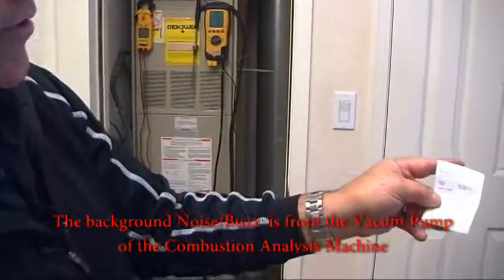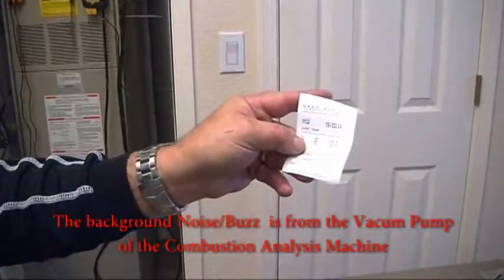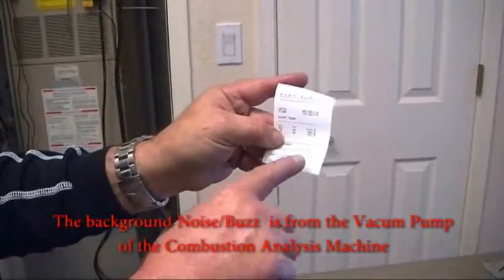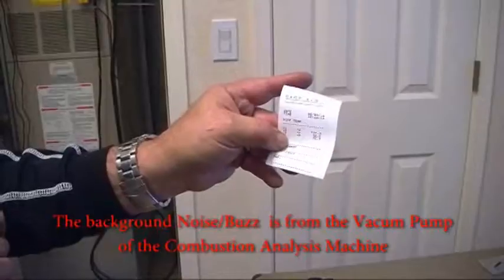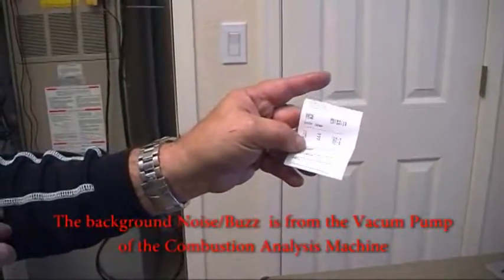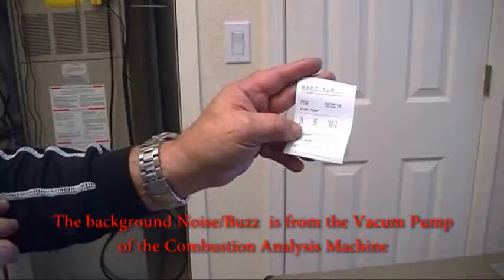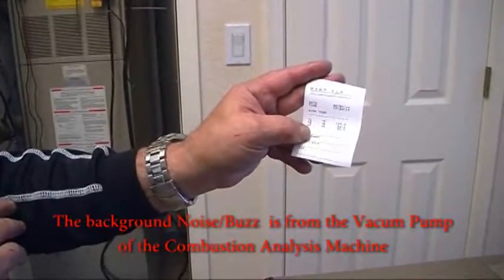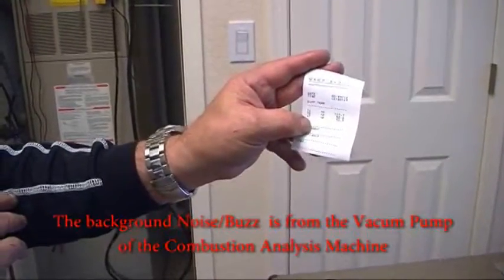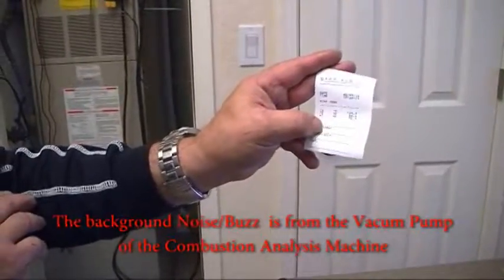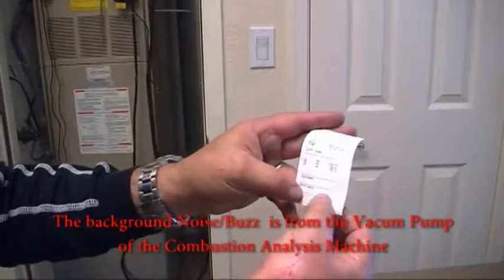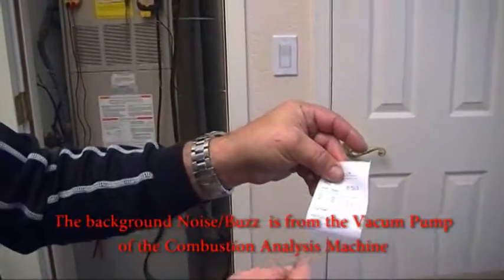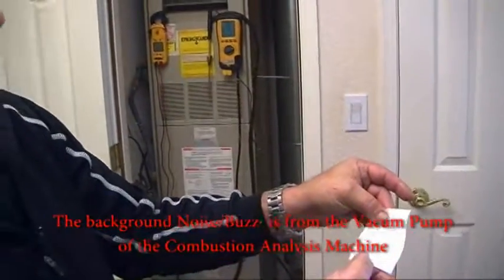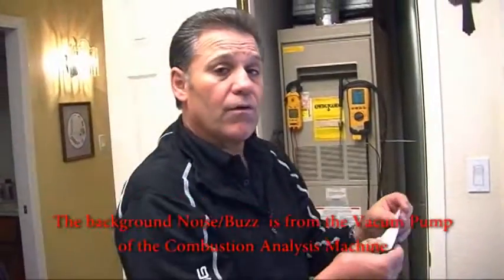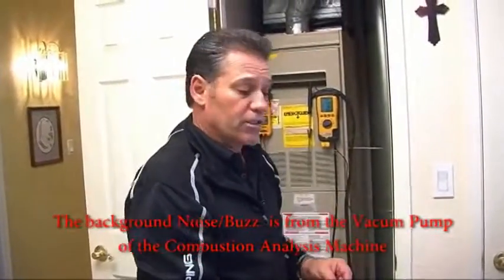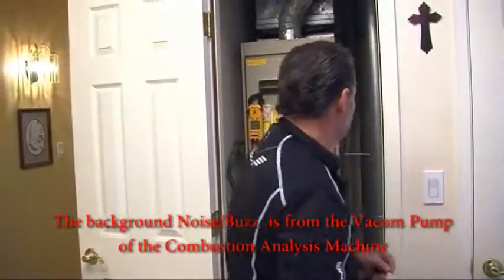It's February the 4th, 2016 at 12:08:14 p.m. Our delta T is 92.9. It's really right where we want it. Our supply air going out is 144.9 or 145 degrees, and our return is 52 degrees. So I will put in the customer's name and have them sign it. The appliance is a Lennox. I'll put the model and serial number here, and this will be part of our report that we give to the customer and that we put at our office for information.